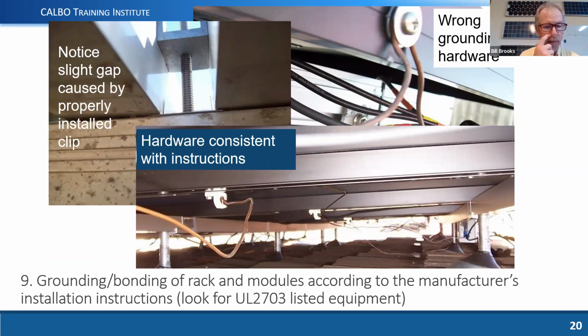So here we're talking about grounding and bonding. And we want to really look for that UL 2703 listed equipment. That's been readily available on the market now for probably 5 years or so. If you're a contractor and you're not using UL 2703 listed grounding and bonding systems, you're probably wasting time or not doing it right. Those are your 2 options.